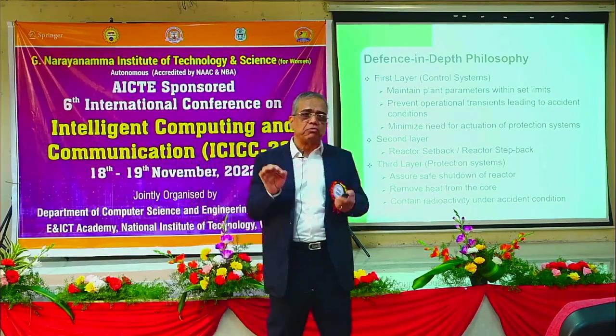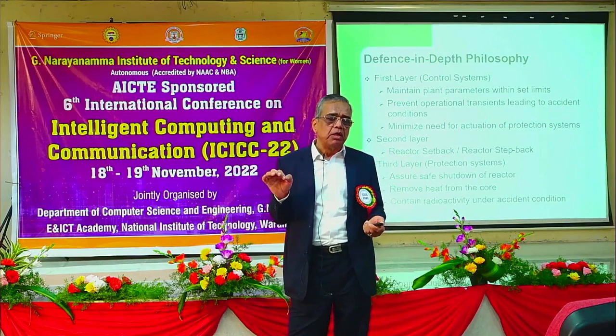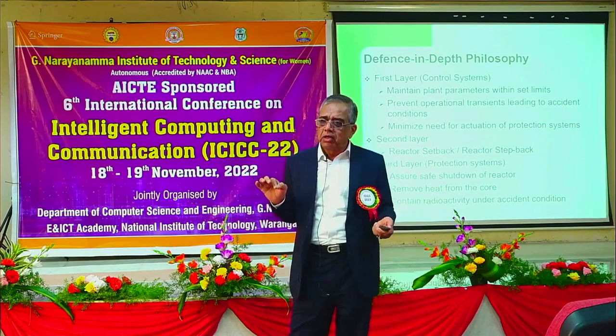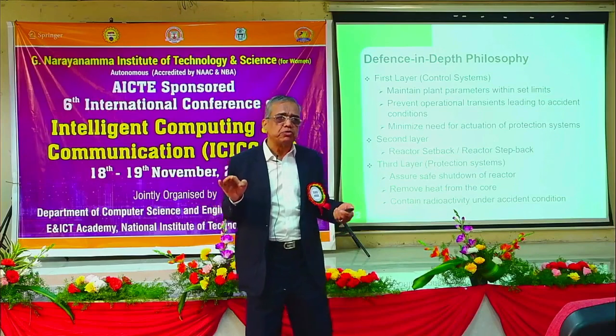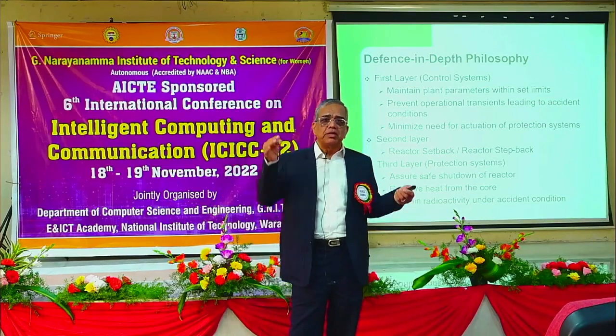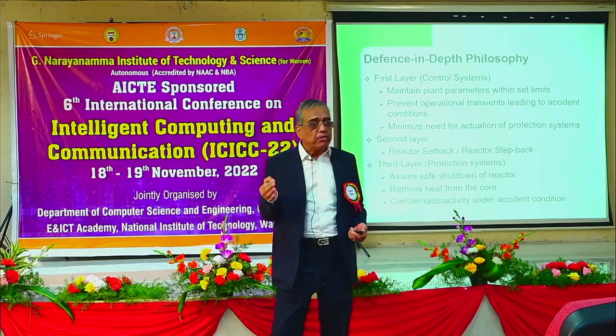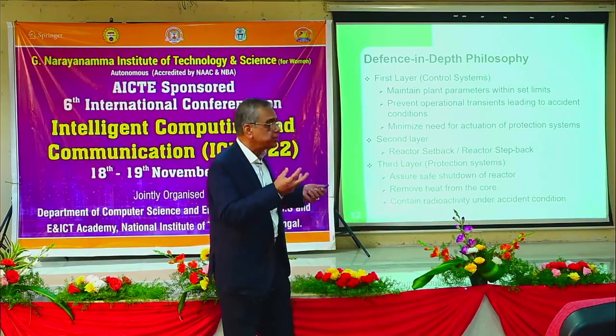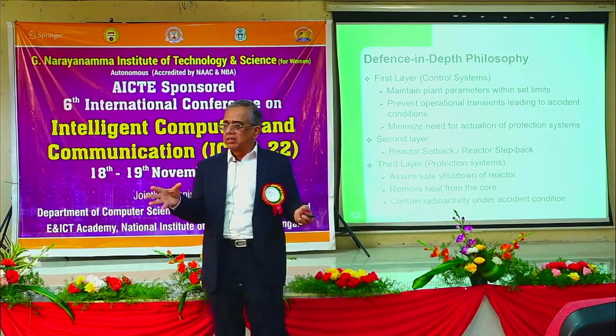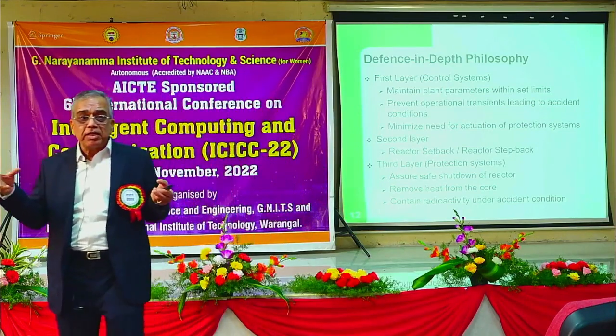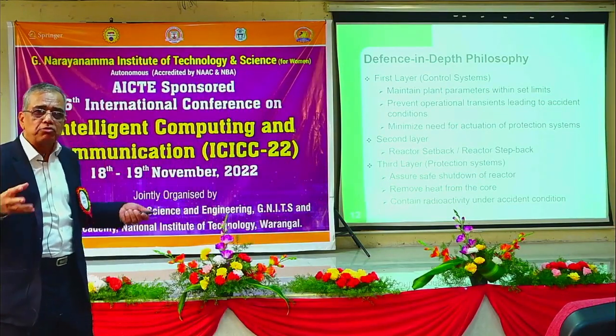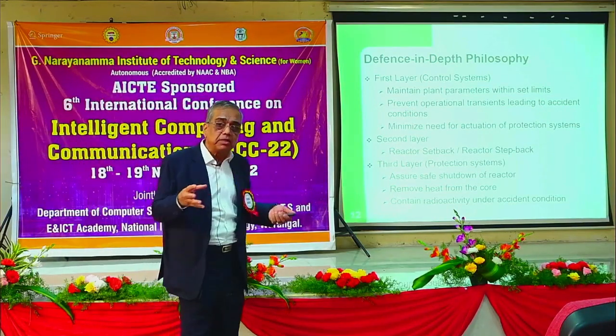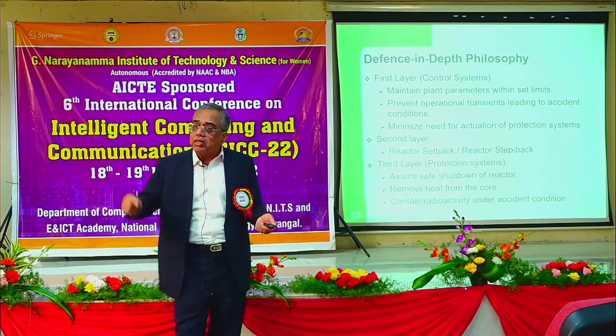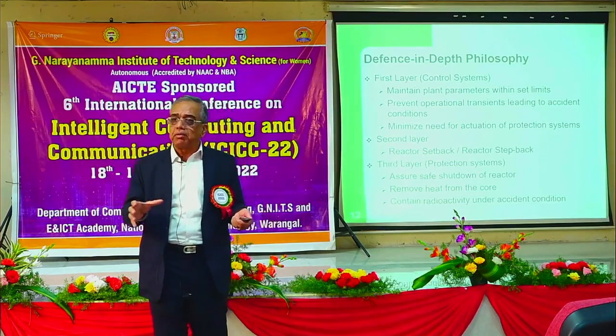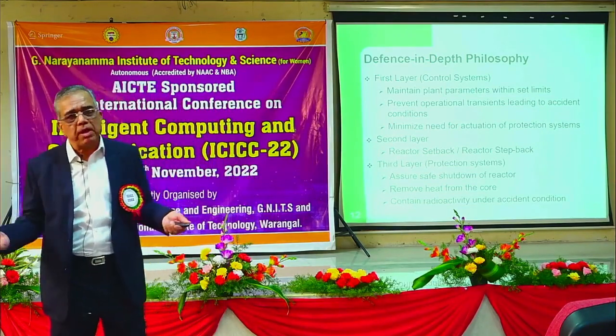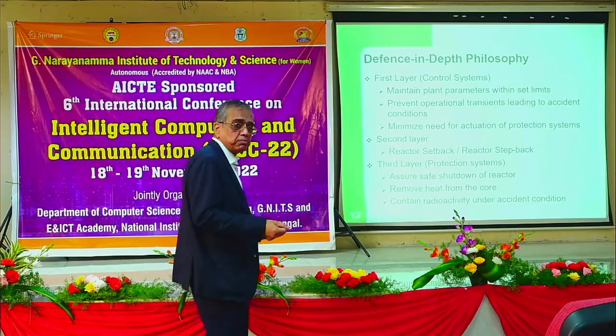There has to be continuous cooling, because even if you shut down, 0.6% of power is still there. Suppose you are working at 1000 megawatt and you shut down, 6 megawatt of power will still be generated by decay heat, because there are fission products giving out nuclear radiation which generates heat inside the reactor. So, still 6 megawatt will be there for a few days. So, you have to continuously provide the cooling. If cooling is not available, the fuel may melt, an accident may happen, all those things are possible.